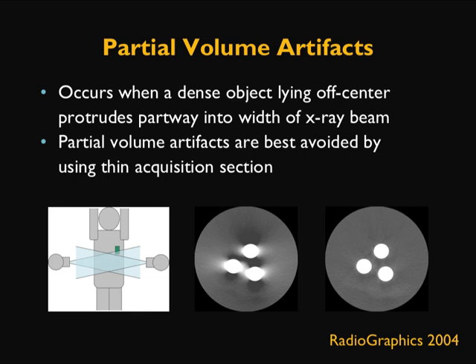Another classic type of physics-based artifact is the partial volume artifact. This occurs when a dense object lying off-center protrudes partway into the width of the X-ray beam. The cartoon shown illustrates a dense object at different points during data acquisition around the patient. The middle image shows three cylindrical objects exhibiting dark bands from partial volume artifact. Partial volume artifacts are best avoided by using very thin acquisition sections, as shown in the third image. Most CT acquisitions today are acquired at the thinnest slice possible to avoid partial volume artifacts and to aid 3D image reconstruction.